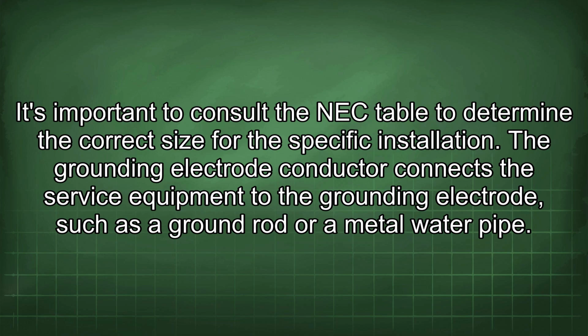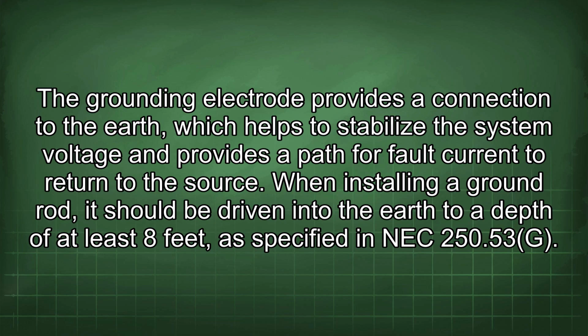The grounding electrode conductor connects the service equipment to the grounding electrode, such as a ground rod or a metal water pipe. The grounding electrode provides a connection to the earth, which helps to stabilize the system voltage and provides a path for fault current to return to the source.